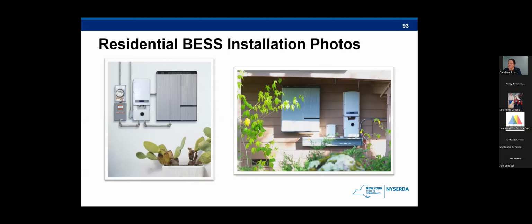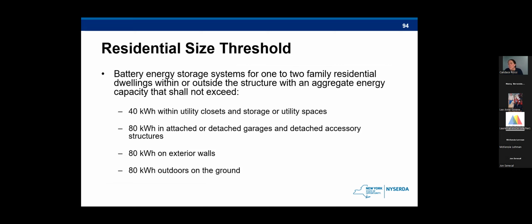So here are just 2 images to give you context of what a residential system might look like. The majority of these are pre-packaged. The residential threshold sizes shown here are from the 2020 residential code and are subject to the uniform requirements, the limitations of which are imposed to ensure the safety of systems. So each individual unit may not exceed 20 kilowatt hours. When you're looking at systems as a whole, the system cannot exceed basically 40 kilowatt hours within utility closets or storage or utility spaces. So basically, if it had its own little boiler room, you could still only be at 40 kilowatt hours.